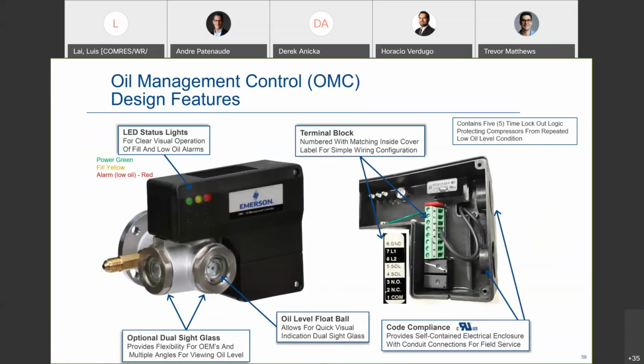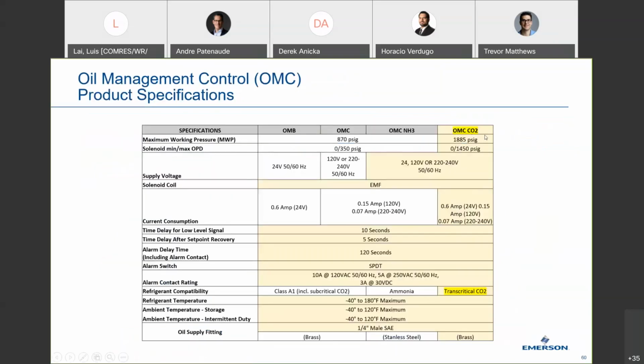It has a 5-time lockout feature that is required for our scrolls. So if it trips 5 times within 30 minutes, there's a lockout feature that forces it to come back and reset, manual reset. So that's kind of a nice feature. There's an ammonia version. The one I'm talking about today is the CO2 version, and I kind of talked about all those things, so I'm not going to spend more time on it, but it has a similar time delay of 10 seconds for low-level signal, and time delay set point recovery is 5, with an alarm time delay of 120 seconds. Those are kind of the standard types of time delays.